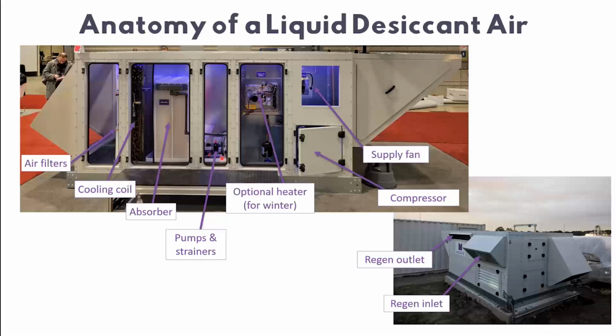We do have those pumps on independent breakers. So if the unit is not being maintained regularly, which we suggest quarterly, filter changes and inspection of those T-strainers. If that's not happening and those T-strainers back up, the pumps are on independent breakers and will trip on high draw, acting like a dirty filter switch would to alert the user that, hey, the product needs to be serviced.